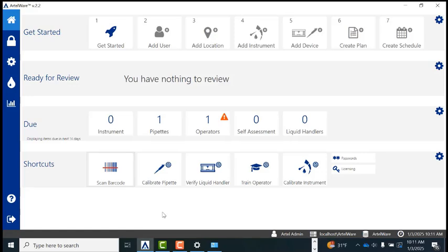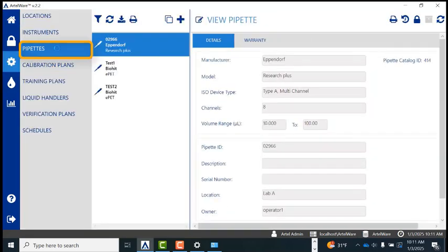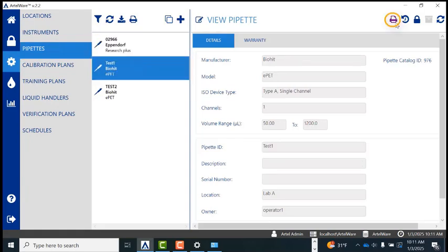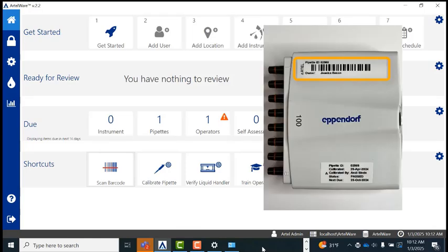From there, if we head back to the menu of ArtelWare, you can test and make sure that your printer is working okay. You can generate a barcode ID label by going to the configuration screen, and in my case, I'm going to select a pipette that I want to generate a label for. I'm going to go ahead and select this Test 1 pipette, and then from there I'll click on the print label icon over on the right-hand side, and I'll select Pipette Label because I want a barcode ID label today. And now my printer has generated the barcode ID label for that particular pipette that I highlighted. You're now ready to generate barcode ID labels as well as calibration or verification labels from ArtelWare.